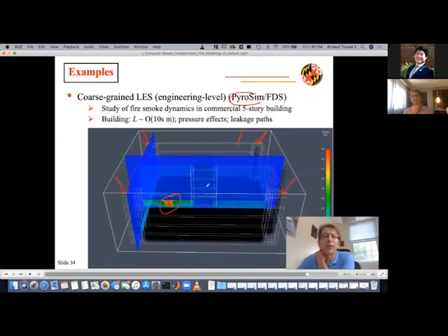Again, the ability of the smoke to move from one space to another depends on the pressure. So here, what we are already doing is checking the capability of FDS to correctly describe pressure effects in tall buildings. The pressure dynamics is complex and is determined by a combination of the stack effect in tall buildings combined with the overpressure brought by the heat release associated with a fire.